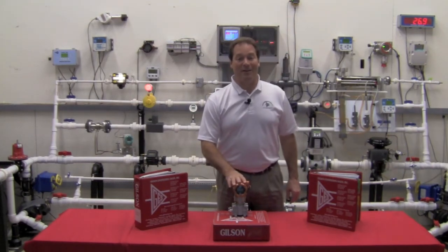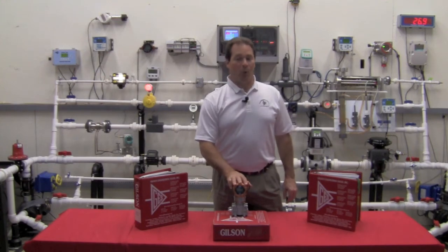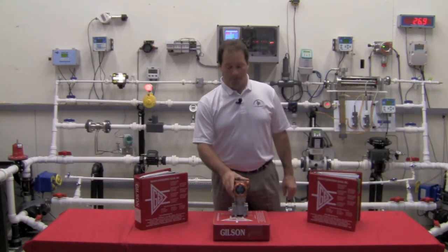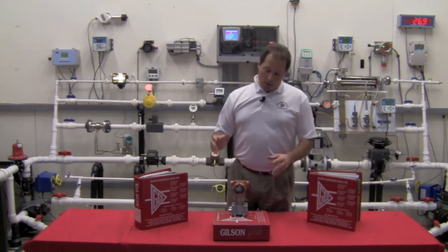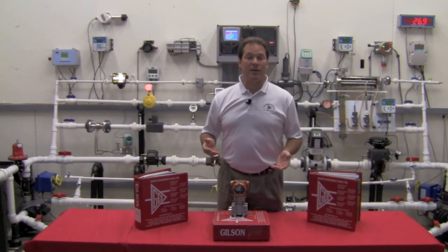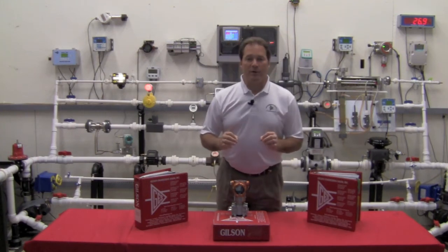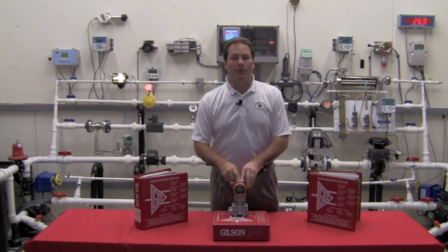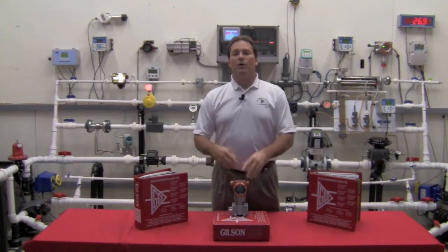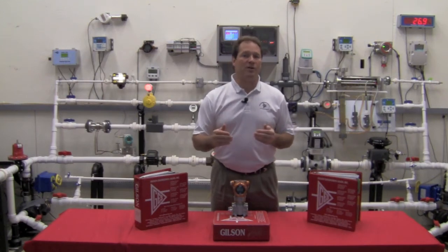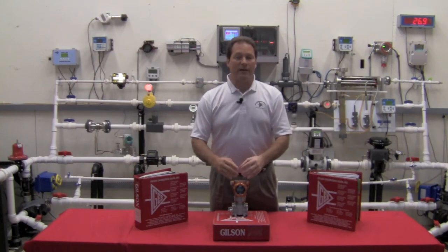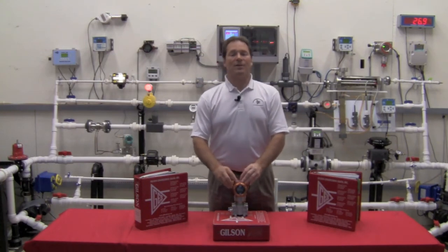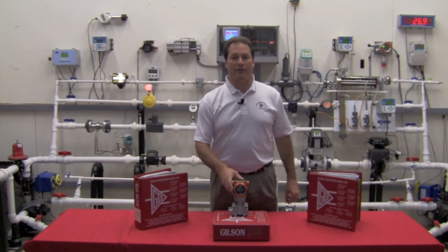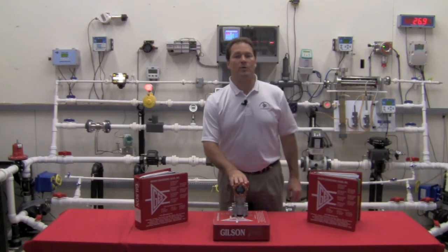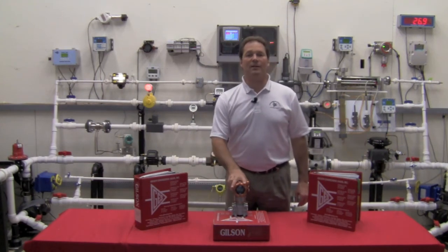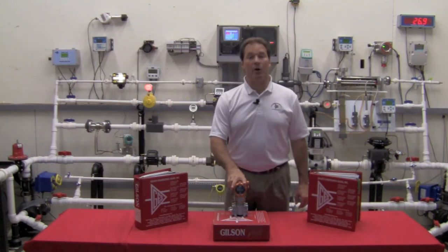What Yamatake does is very different. We put every transmitter, 100% of them, into an environmental chamber. We let it sit there for 24 hours minimum. The whole time we're fluctuating the pressure, fluctuating the temperature, and we are recording the results of those fluctuations on a double EEPROM that resides inside the transmitter itself. Knowing what the effects of a changed temperature and a changed pressure are, and mounting that on the double EEPROM on the transmitter, allows us to have the equivalent of hundreds and hundreds of points of calibration. That allows us to operate much more stably over a period of time. That's one of the things that allows us to offer plus or minus 0.1% stability over a 10-year period.